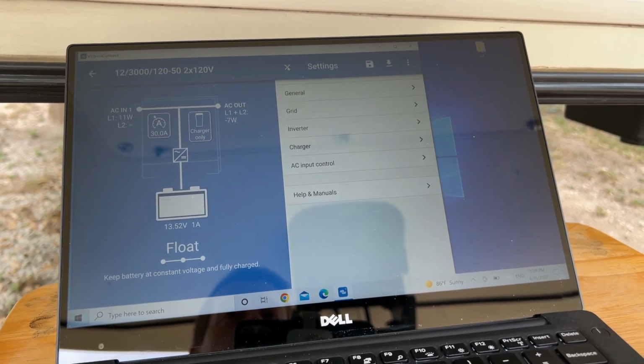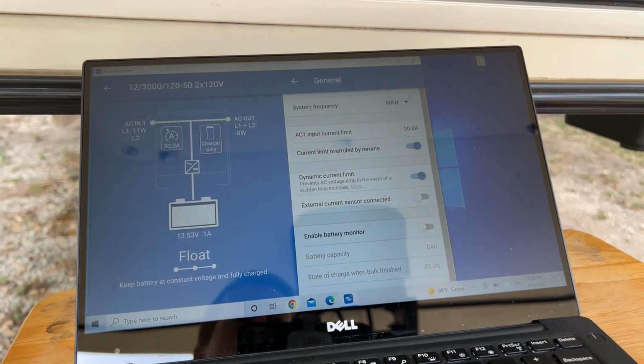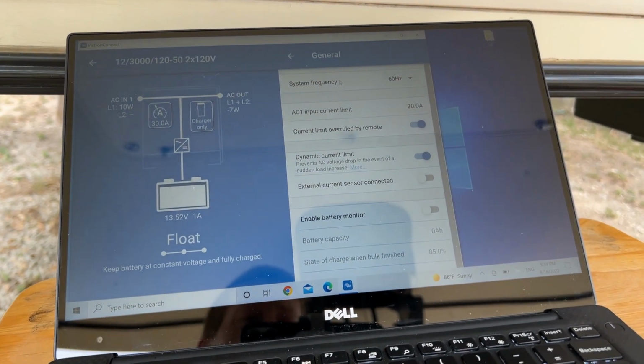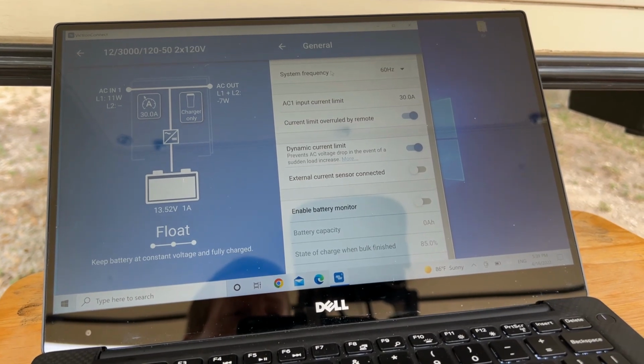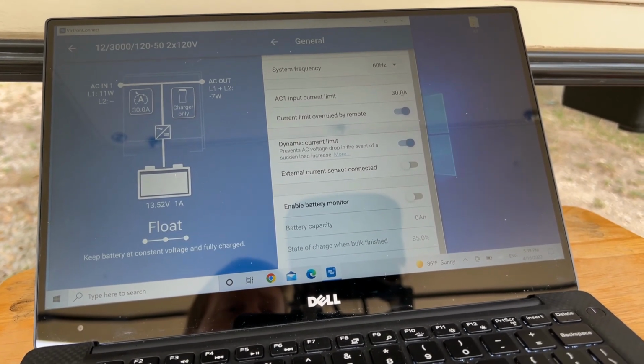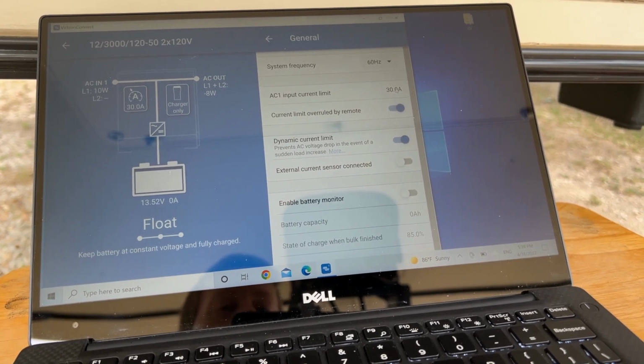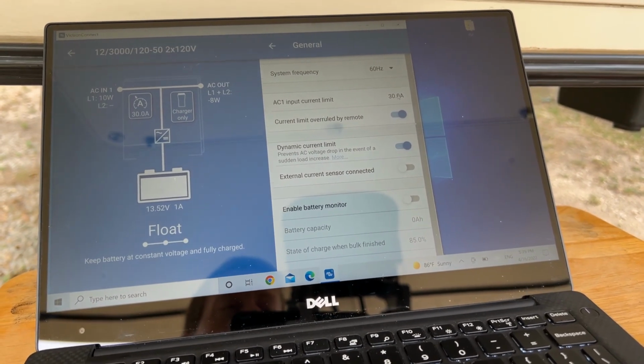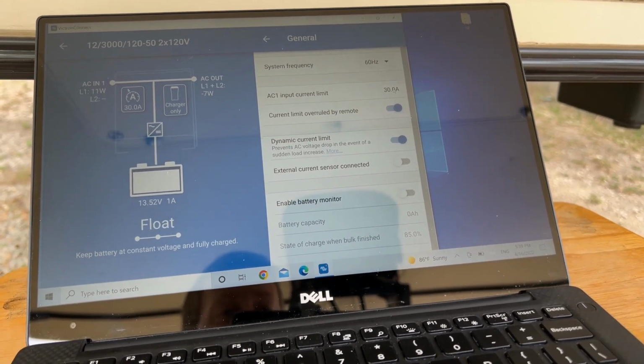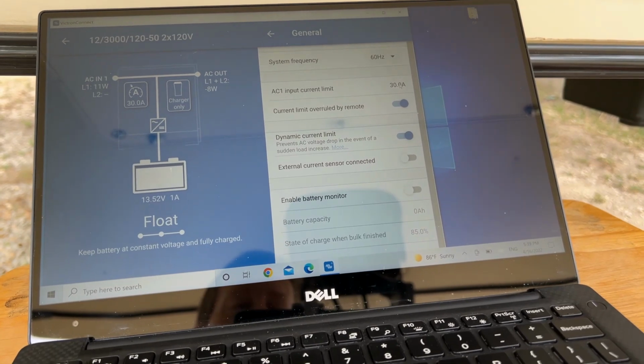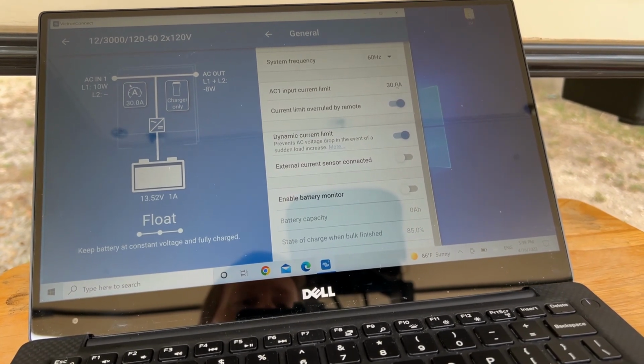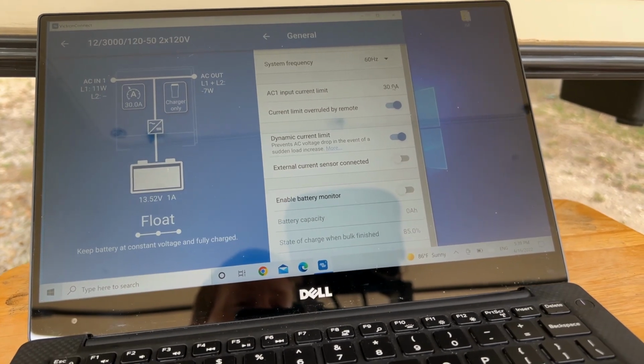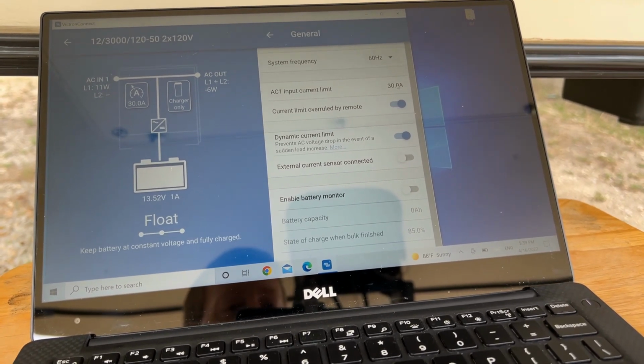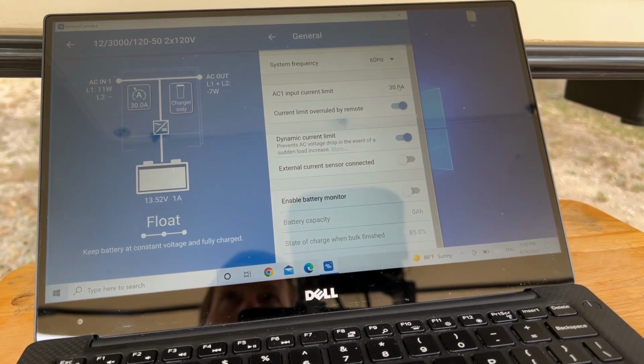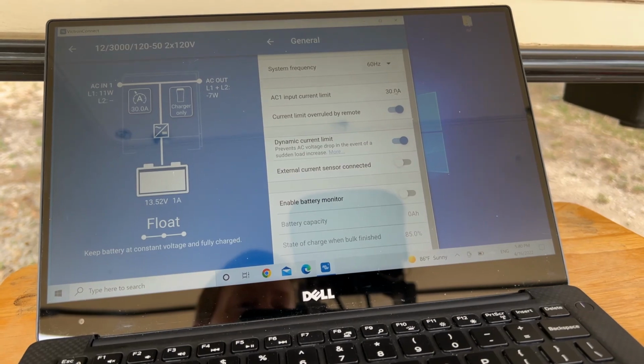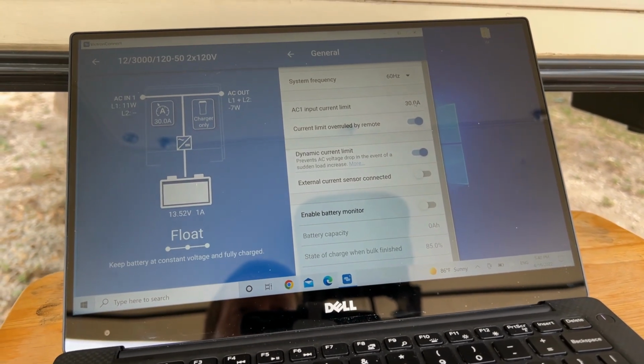Next up, once you get the charger settings set, there are a few other things you can go through. Obviously in North America, we're on 60 hertz AC power. Right now I've got my current limit set to 30 amps, and I'll talk about that in a little bit. You can change that from the Cerbo GX touchscreen, the Touch 50 that I have. That's where I set my input limit. Right now I'm on a 30 amp circuit, so I don't want to overload that and trip a circuit breaker. It does say the current limit is overruled by the remote. That is the Cerbo GX touchscreen. That is the remote.